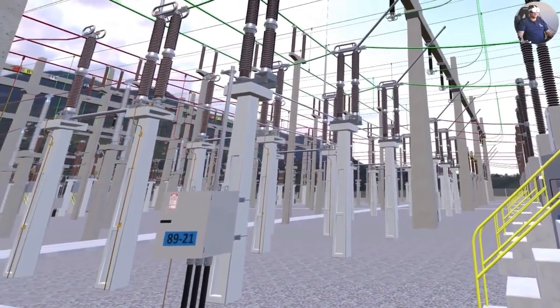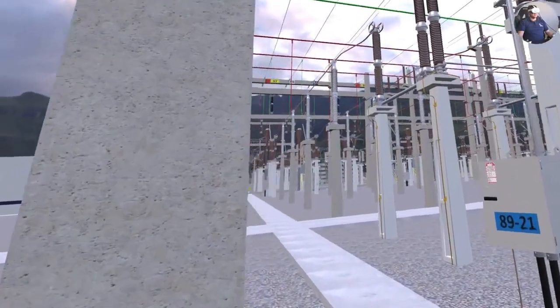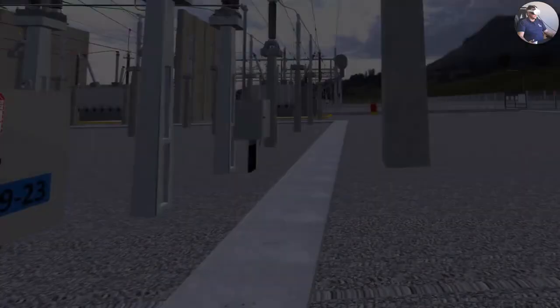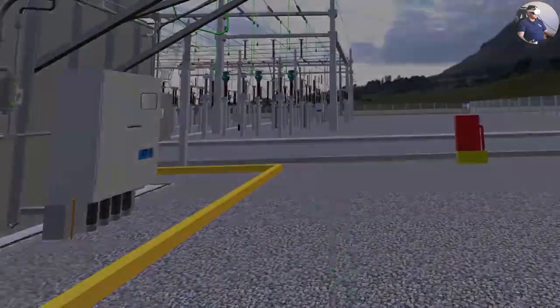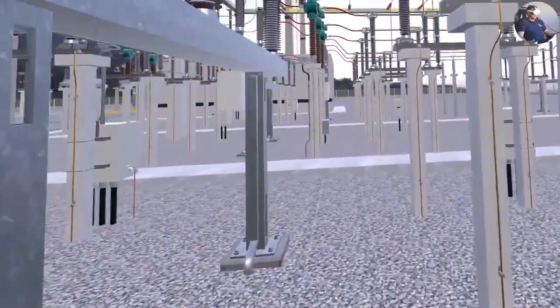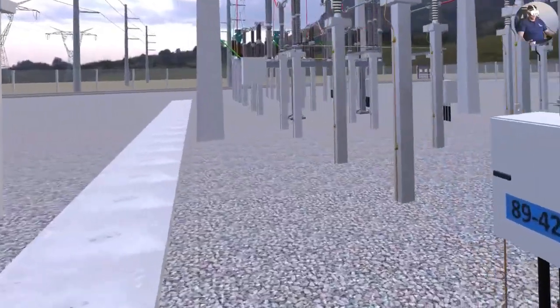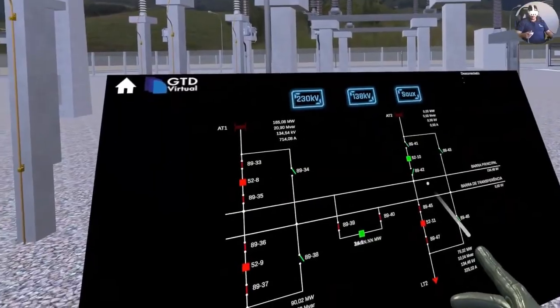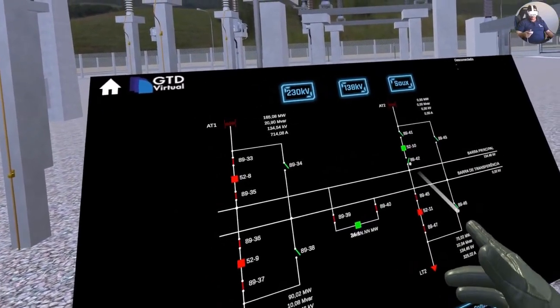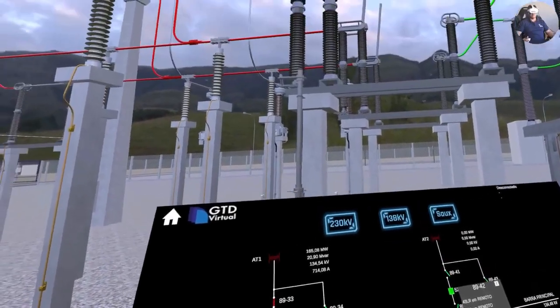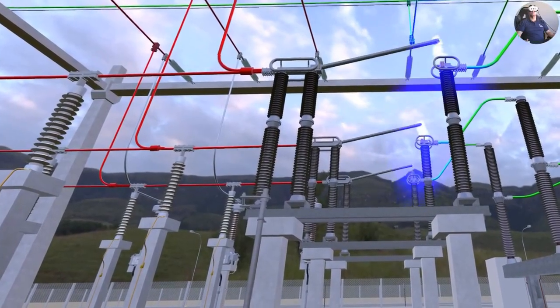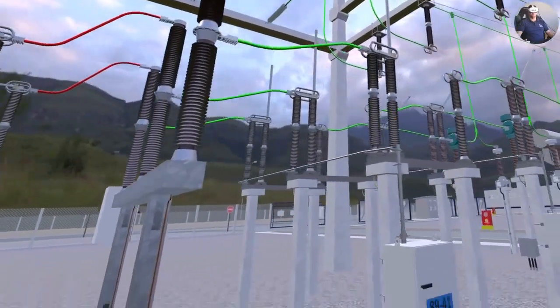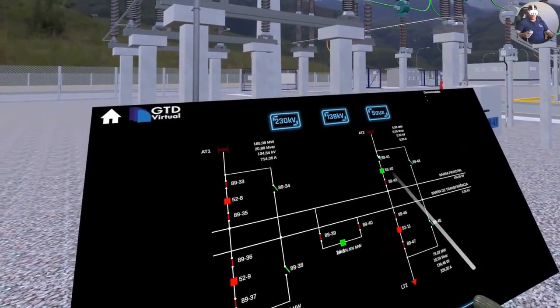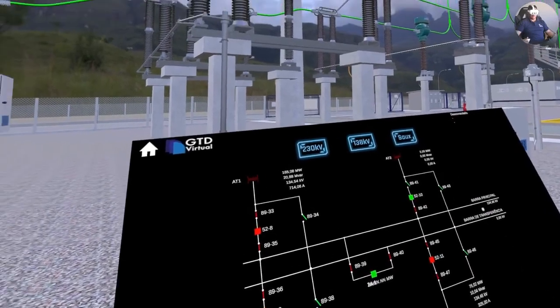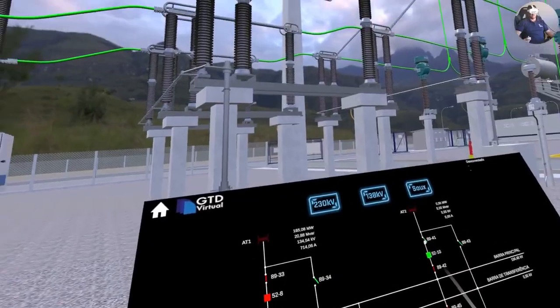So we're going to start these maneuvers, guys, by closing the disconnect switches here in the sector. Let's start over at the 138 kV sector. Okay, so let's go. So we're going to close here. Now let's take a careful look at the main bus disconnect switch, which is the 89. Let's go ahead and check the operating code for it, which is 8942. Let's perform this closing here. 8942. Just to confirm, the number is 8942, okay? Let's close it right now. Awesome, switch closed successfully. Let's close 8941 here. Switch closed.